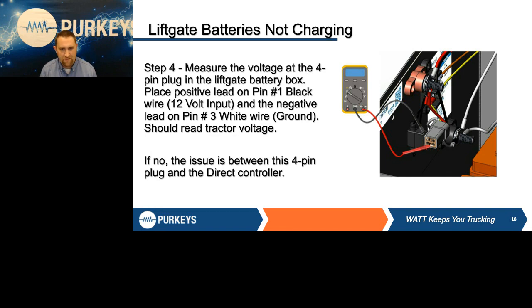You want to measure the voltage on pin number 1, which is your black wire, that's your input positive. Then put your negative lead on pin number 3, which is your white ground wire. If you look on the back of that 4-pin plug, it's numbered, but I put the wire colors in here to make it easier. Just like at the front, you want to read that input voltage, you want to read tractor voltage. If not, then there's got to be an open circuit from this 4-pin harness to the direct controller up front. So repair that circuit and move forward.